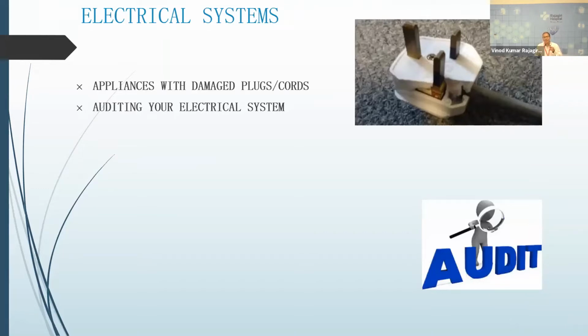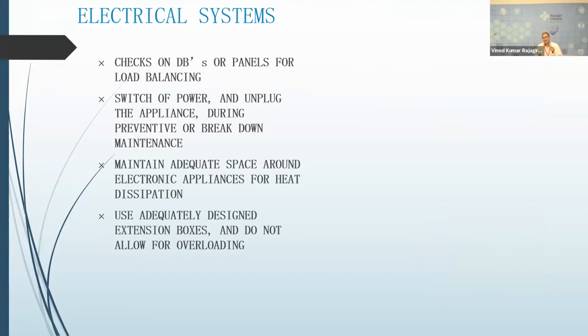And with very minimal maintenance, damaged plugs and cords are being used. NABH as well as NBC say that we should have regular auditing, which is also a missing factor, which leads to damages and fires regularly. When it comes to the electrical panels, equal load balancing is important across the phases. So a proper study of the system is important. Use thermography, check the design load and the connected load, and ensure load balancing is very clear. And when the maintenance team does their maintenance, ensure they unplug the appliance after switching off the power, whether it is preventive or breakdown maintenance.